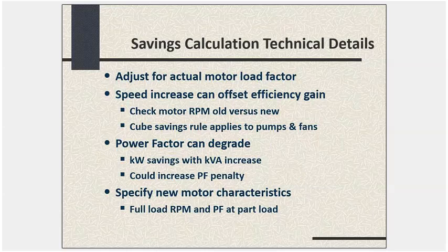Something to think about - then the power factor can also degrade. That can occur, and you have to consider whether it could increase your power factor penalty. When you're replacing equipment, if you're matching a variable frequency drive of some kind to a motor, you better be sure they're going to work together appropriately. If they don't, sometimes you can be burning out your old motors with new variable frequency drives, and that's not a pretty picture. So you want to specify the new motor characteristics - full load, RPM, and power factor, etc., at part load.